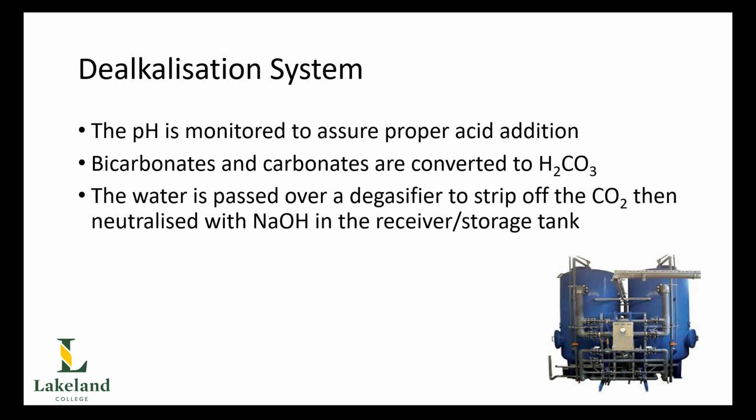Now, the idea here is that we have to monitor that pH to ensure we only add enough acid required to get us down to that free mineral acidity point. And also, of course, making sure we inject enough acid to get us into the pH of free mineral acidity, which ensures we have removed our alkalinity.